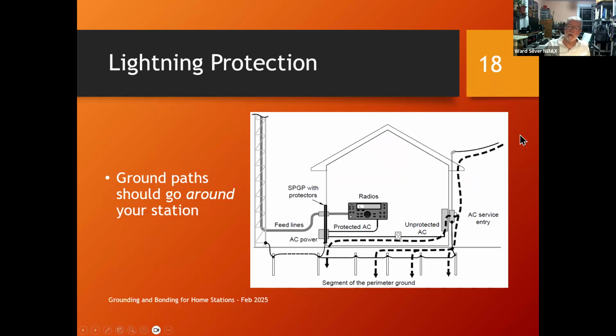So this time the lightning comes in on the AC line. Very common. It comes down to your AC service entry. It says, here's a really good external ground system. I've got my perimeter ground: ground rod, ground rod, ground rod. You really build up your shoulder muscles pounding in these ground rods. And if you've got a rocky installation or something like that, the NEC allows you to bury it in a horizontal trench or drive it in at an angle. It doesn't have to be vertical.